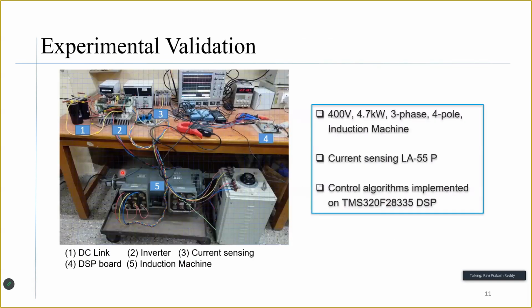So once we had done the validation, the simulation validation and analytical validation, we have also conducted experiments, and the photograph of the experimental setup is shown over here. So we have the main grid, the three-phase grid, which is then passed on to a three-phase auto transformer array, Variac, and the output of this three-phase transformer is connected to a DC link, and the DC link is connected to the three-phase two-level voltage source inverter, which is shown over here with the gate drives present on the top, and we have used Semikron IGBT switches over here.